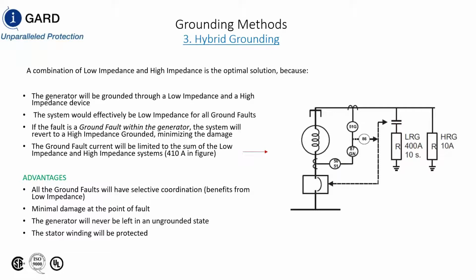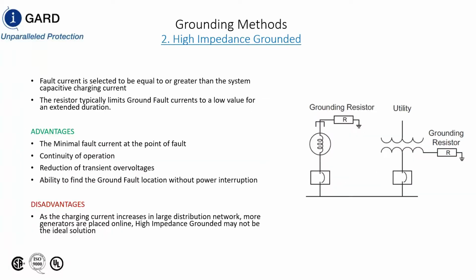And this is the hybrid high resistance grounded system, so that each generator can have a ground return path of 400 amps in this particular case, and 10 amps. So when there's a through fault, the maximum fault current is going to be 410 amps, but under differential conditions, if you have a stator winding fault, this breaker and this breaker open, allowing the generator to coast down with a 10 amp resistor, and it's going to limit the fault current.